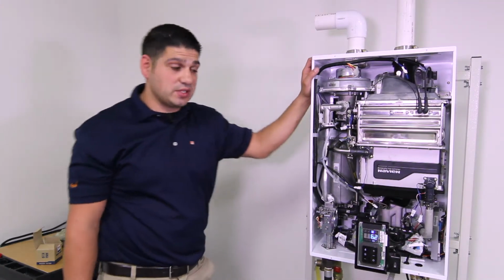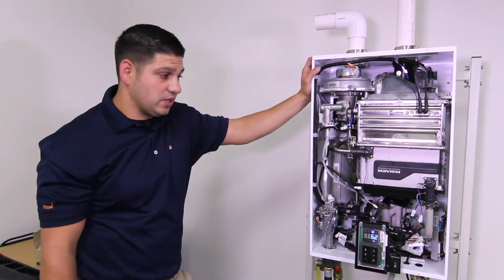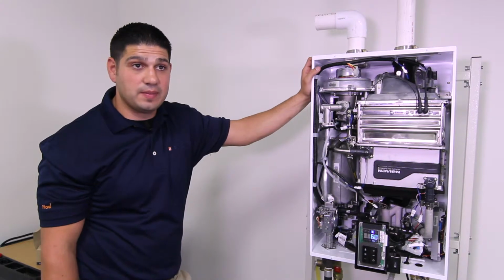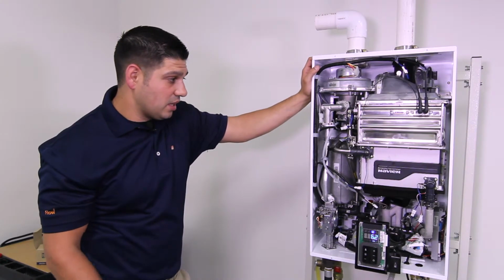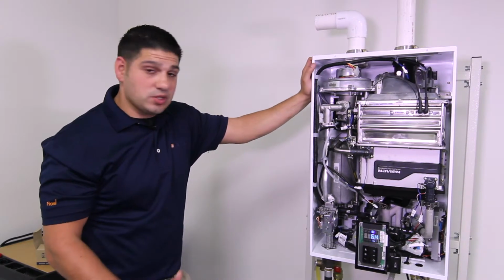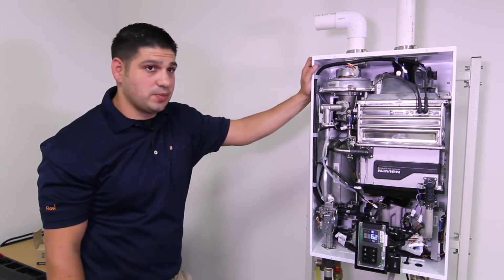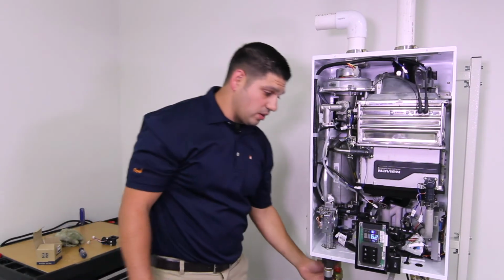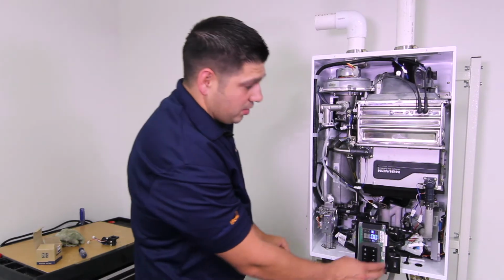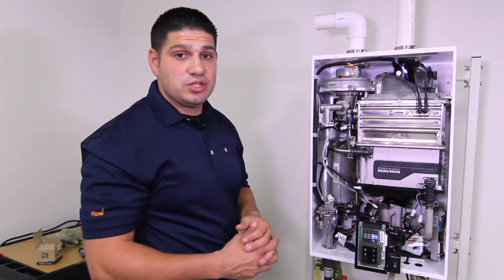What that's telling me is we have 6.2 GPMs flowing through this unit, telling me that my flow sensor is working perfectly fine. And now that we've gotten this far, we know that the unit's working fine. Flow sensor is doing exactly what it's supposed to be doing. We're going to go ahead and turn the unit off, keep the power on, put the cover back on, and we're good to use our water heater.